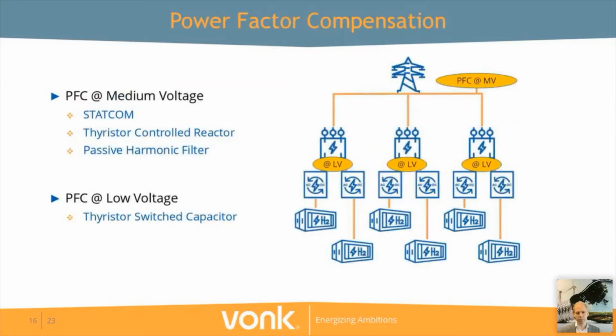There are two ways in which you can apply power factor compensation. The main approach is to set it either at medium voltage or at low voltage. Medium voltage is a centralized approach, whereas low voltage is a decentralized approach. The main advantage of applying power factor compensation at medium voltage is that you can not only cover your own installation, but you can perform power factor compensation at grid level. So also when you have interfering power supplies from other applications, you can improve the overall performance of your local grid. There are three ways in which you can apply power factor compensation at medium voltage level.